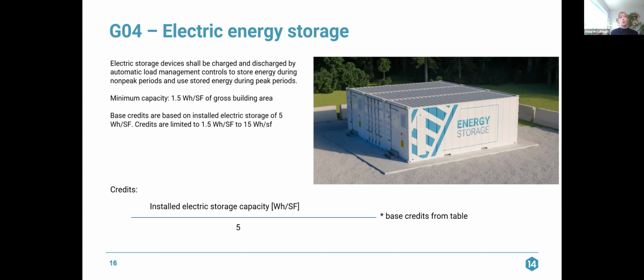The minimum capacity required to achieve credits under the electric energy storage is 1.5 watt hours per square foot of gross building area. And the base credits are based on an installed electric storage of 5 watt hours per square foot. So if you have less than 5 watt hours per square foot, your credits will be derated. If you have more than 5 watt hours per square foot, your credits will be increased. You can only take credit for up to 15 watt hours per square foot of electric energy storage batteries.